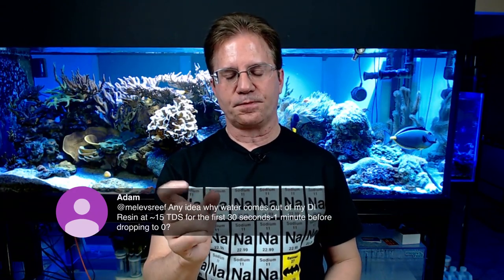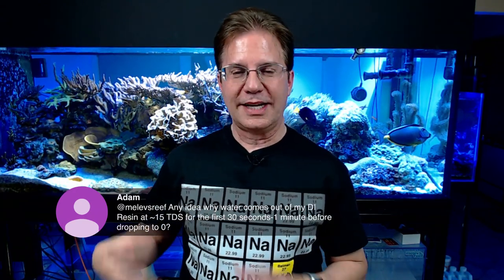You don't want that initial burst of 100, 200, 300 TDS to even go into the DI. So you want to put a T fitting before the DI and run some tubing as your purge line. You open the valve, wait 90 seconds.